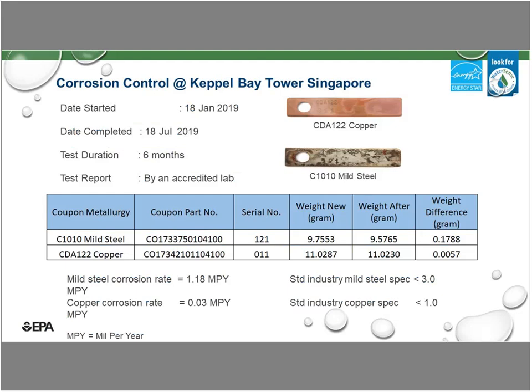Okay, so of course the other one is about the corrosion. You can see that on the mild steel and the copper coupons that we put in for 6 months, our mild steel corrosion is 1.18 mils per year, and copper is 0.03 mils per year. So this is well within the standards set by the Cooling Tower Institute in the US. They have this kind of standards that tell us we are able to control corrosion.